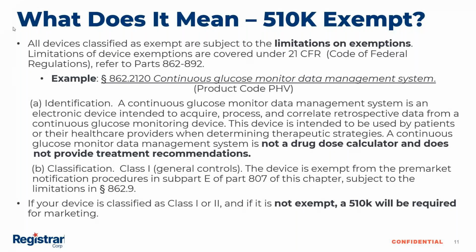Now, the definition or identification says a continuous glucose monitor data management system is an electronic device intended to acquire, process, and correlate retrospective data from a continuous glucose monitoring device. This device is intended to be used by patients and their healthcare providers when determining therapeutic strategies. A continuous glucose monitor data management system is not a drug dose calculator and does not provide treatment recommendations.